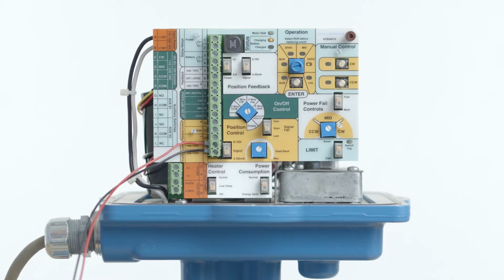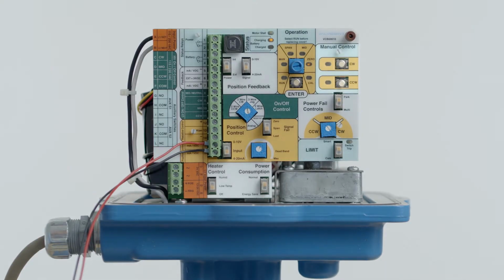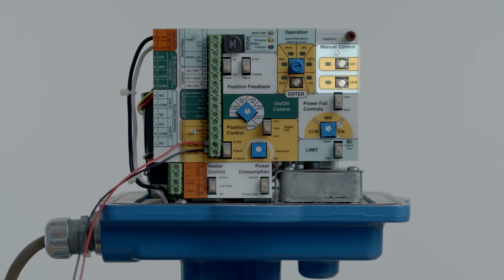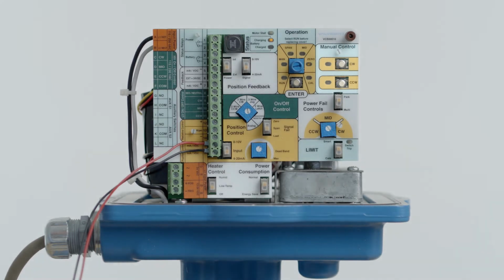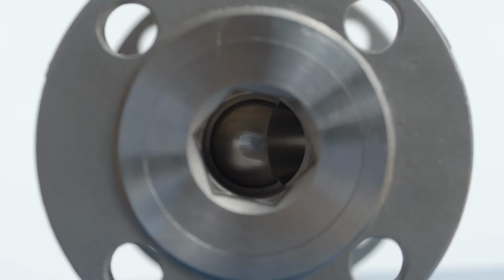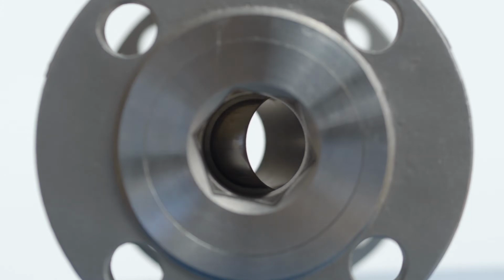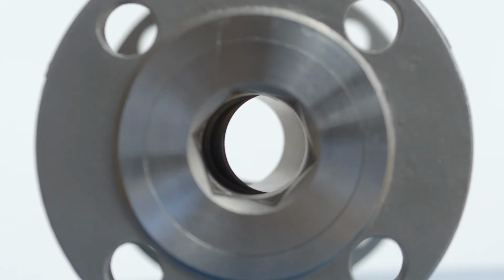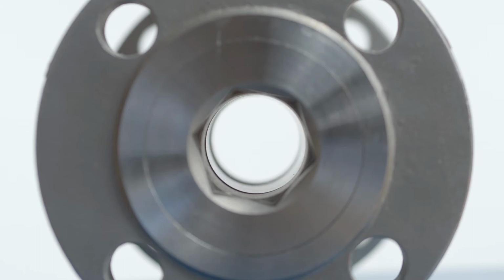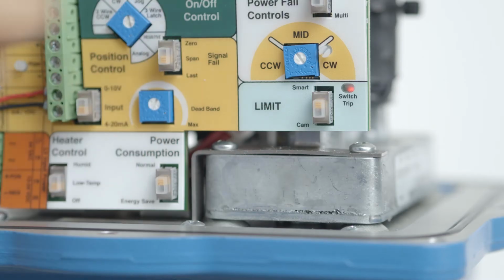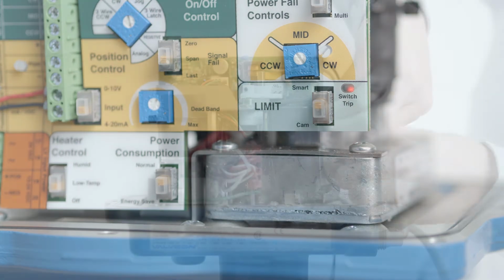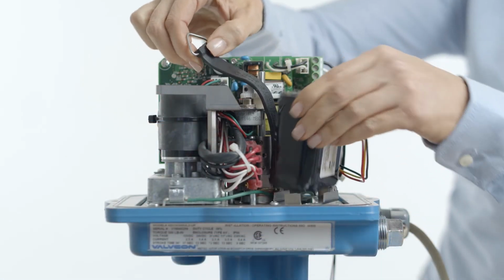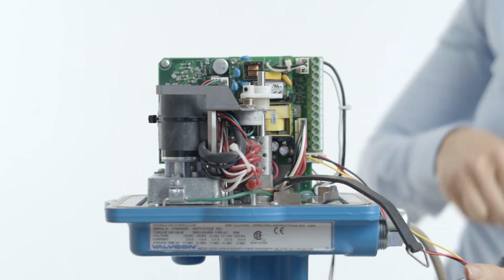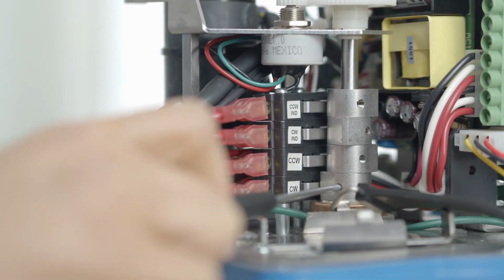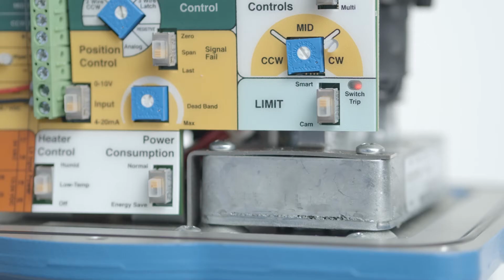Drive the actuator to the desired clockwise position using the CW or CCW push buttons. If the stall LED begins to flash, check to see if the limit switch cam is preventing the actuator from reaching the desired 0 end of travel. If this is the case, the switch trip LED will be illuminated. If necessary, back the cam off so it trips the switch slightly beyond the desired end of travel, at which time the switch trip LED will go out.